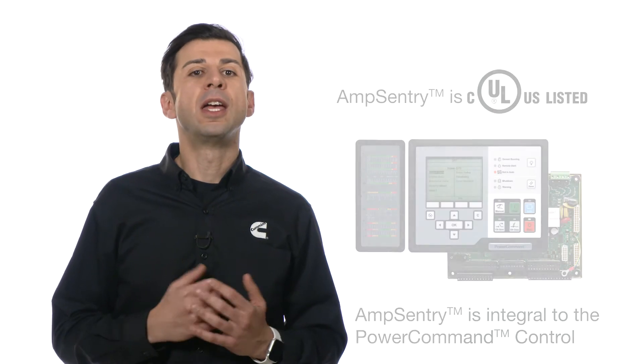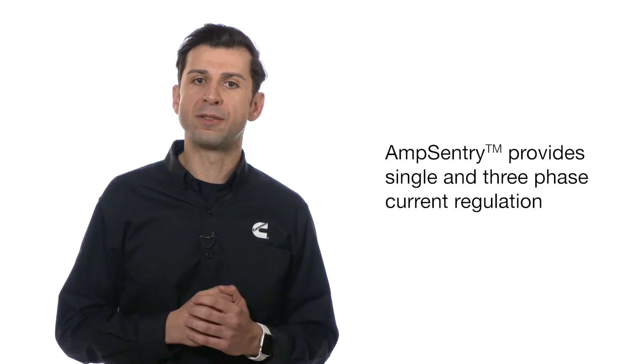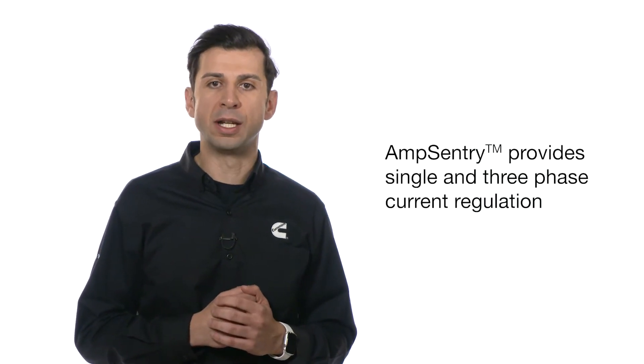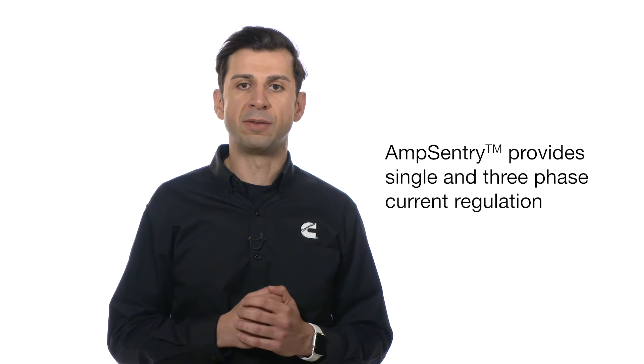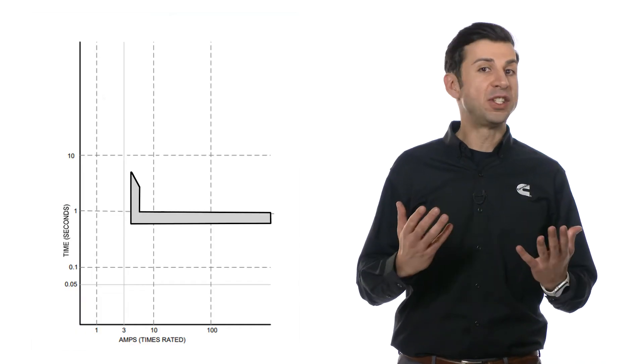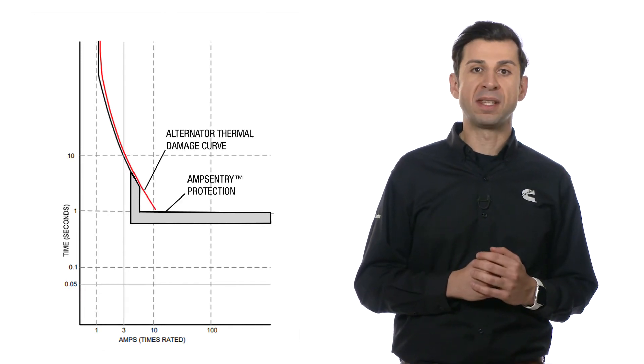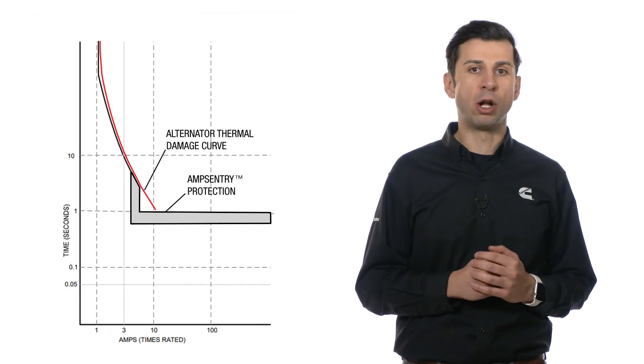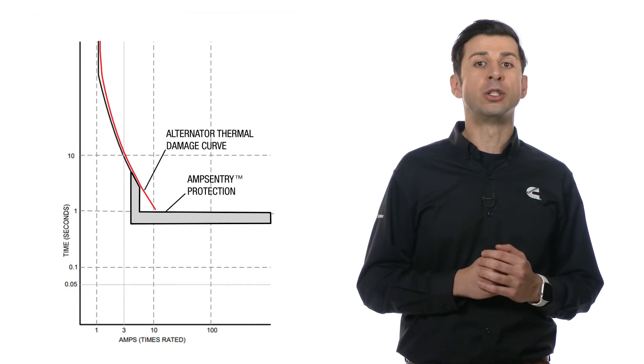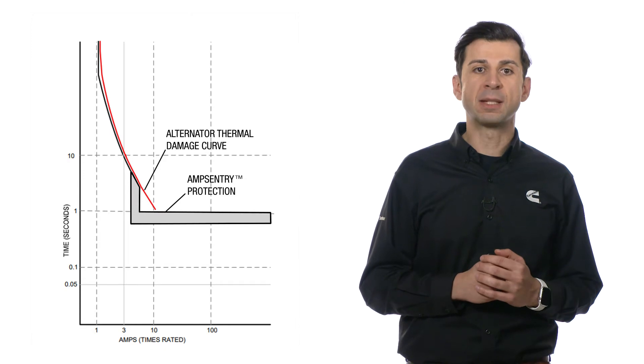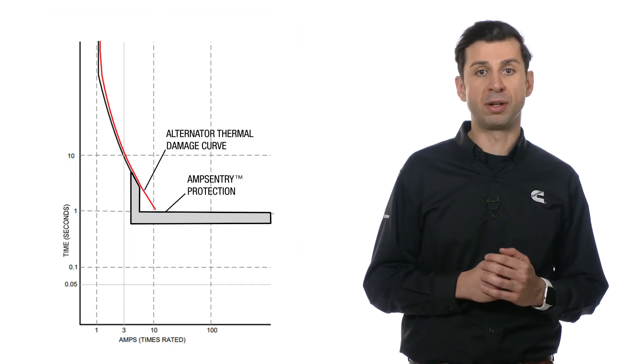It provides single and three-phase fault current regulation so that downstream protected devices have the maximum current available to quickly clear fault conditions without subjecting the alternator to potentially catastrophic failure conditions. As you can see from this graph, Amp Sentry hugs the alternator thermal damage curve to provide the maximum and best protection for the generator set.